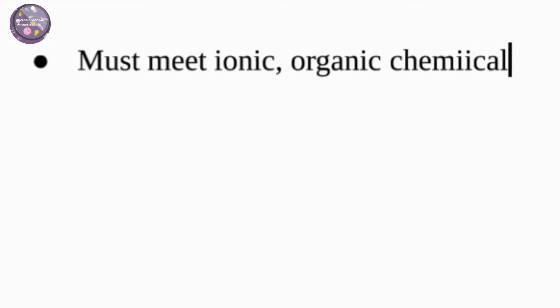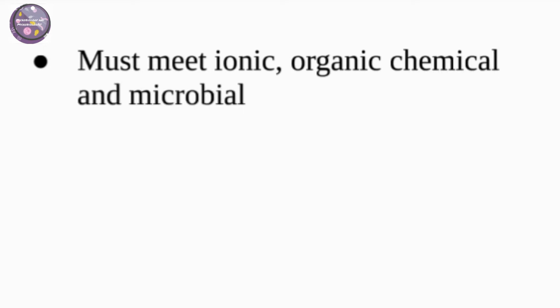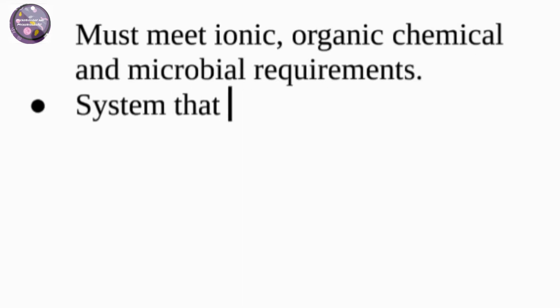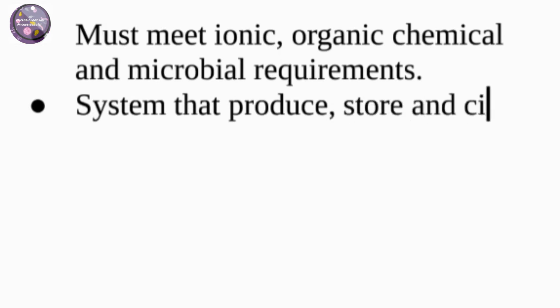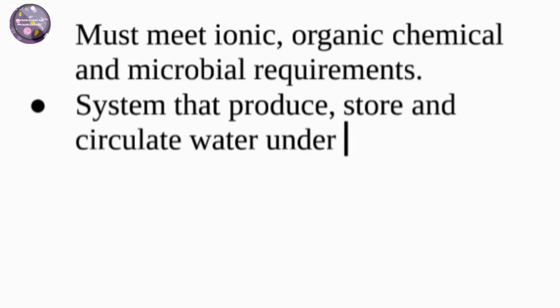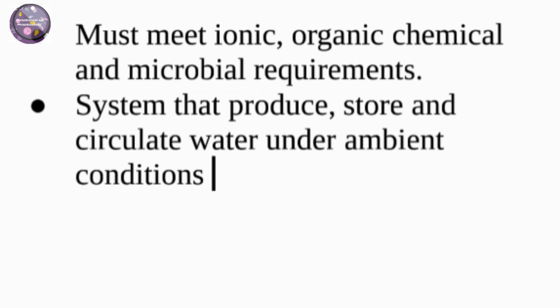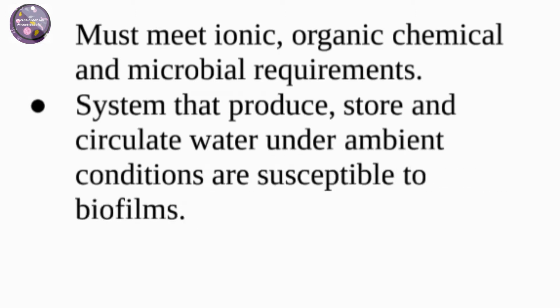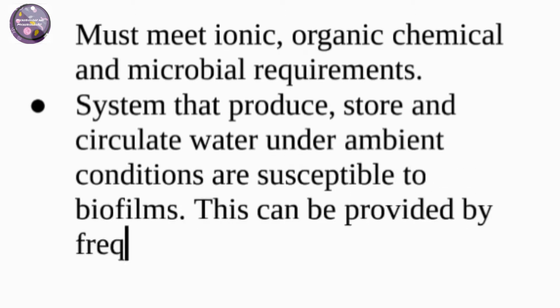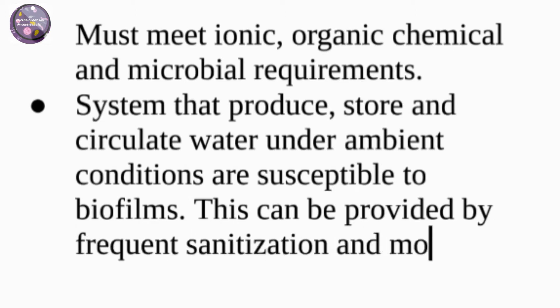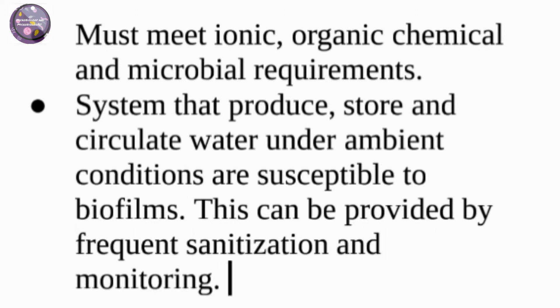Purified water must meet ionic, organic, chemical, and microbial requirements. Systems that produce, store, and circulate water under ambient conditions are susceptible to biofilms. This can be prevented by frequent sanitization and monitoring.